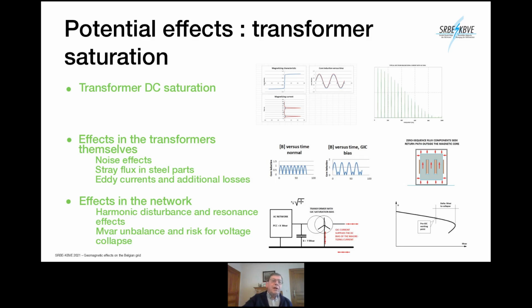What are the effects of this DC saturation of transformer? You get effects in the transformers themselves, and you get effects in the network. The first effect in the transformer, which is maybe annoying but not so serious, is that the noise of the transformer increases enormously. For two reasons. One reason is that there is a 50 hertz component appearing, whereas in normal operation it is a 100 hertz noise component only. You get a 50 hertz component and also a much bigger induction level and much bigger magnetostriction, which means deformation of the steel, and which is in fact the link between the flux and the sound.